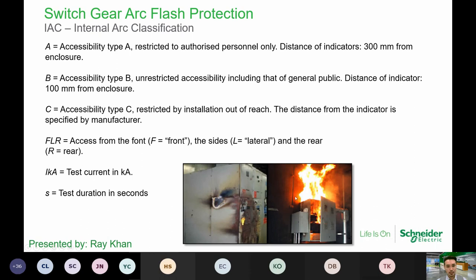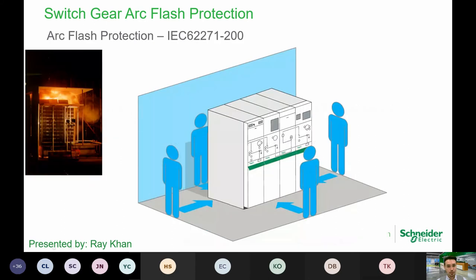So using the high-speed camera, you can see that the flames actually go up the weak point and push the fire upwards itself. So this one focuses more on the FLR requirement. So the front, the side, the rear. So the whole objective in here is that when they do the arc test, they need to ensure that the four sides of the panel are safe.